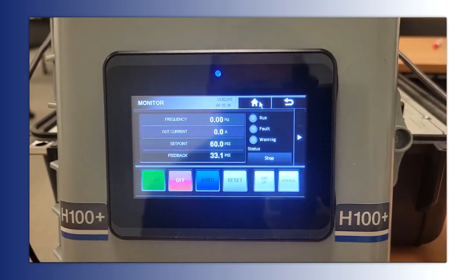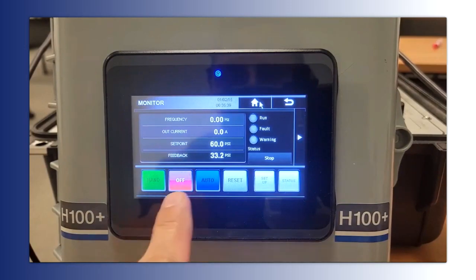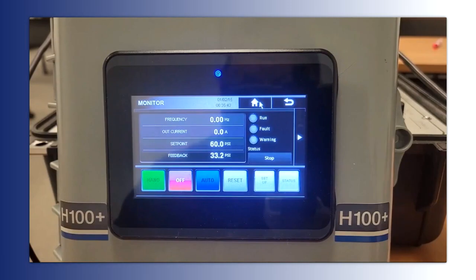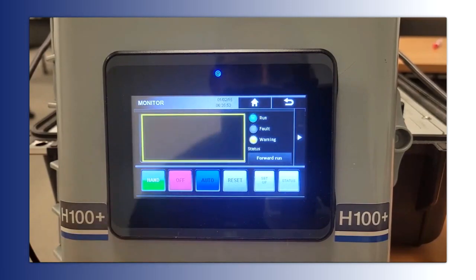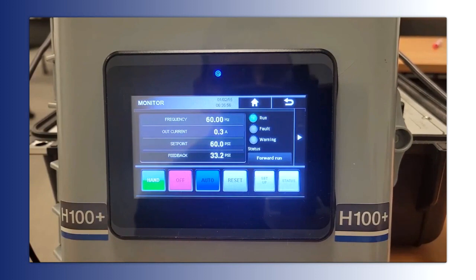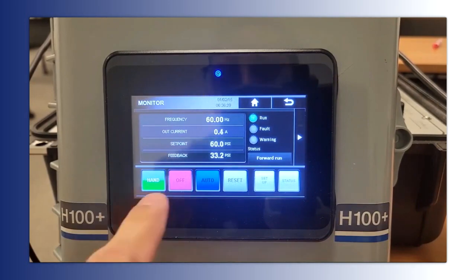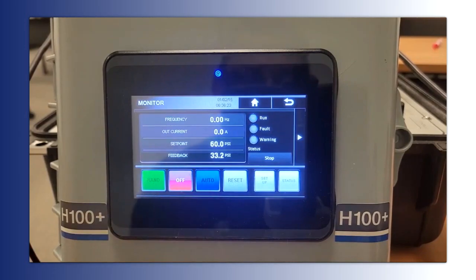Just like we mentioned on the H100 Plus keypad, we have our hand off auto buttons, so those are right here. All of these are mapped over Modbus, so we're actually communicating Modbus to the drive, and this is just a plug and play option. So for example, if I wanted to run in hand, I'd hit the green hand button. You can see that thrust mode message came up. This has actually been set up with a thrust frequency of 30 hertz. So 0 to 30 hertz in 1 second to pretend that we're on a submersible pump. That'd be a normal feature you'd program in there. So right now we're just running hand. This is a good way to check direction or run while maybe you don't have pressure feedback set up and stuff like that. And you get it off, and then auto mode is actually going to run our PID loop.